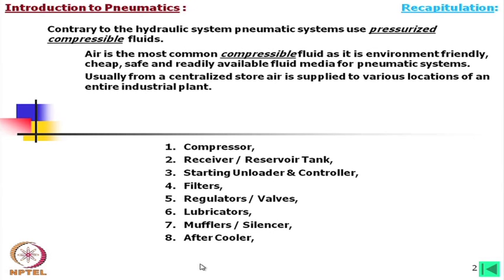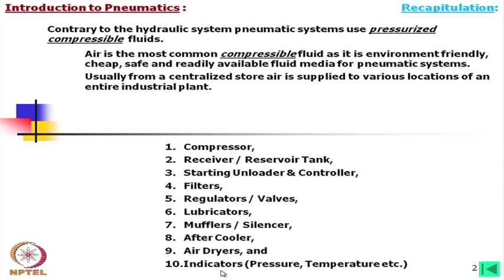Now, we need an after cooler. This after cooler is not after the utilization, in fact it is before the utilization, because when the air is being compressed, a lot of heat is generated. So it needs to be cooled before being utilized for further work. Also the air contains water particles, so it needs to be dried, so we need a dryer. And apart from that, different sorts of indicators, pressure and temperature, are required.